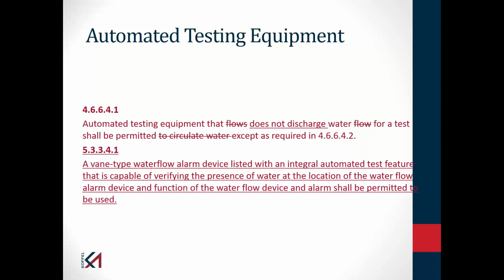We are often criticized, we being the 25 committee, for requiring you to flow so much water in water flow tests, main drain tests, backflow preventer tests, fire pump tests. And of course, in some instances, we've even had situations where the state fire marshal might say, don't flow water because of a water shortage. That happened in California a number of years ago.